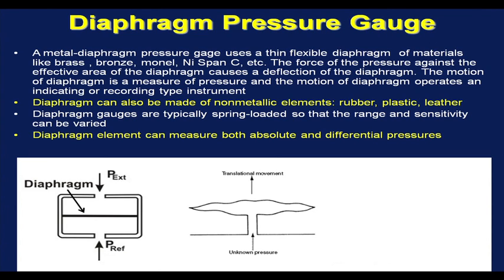Let us now talk about the diaphragm pressure gauge in a little more detail. A metallic diaphragm pressure gauge uses a thin flexible diaphragm of materials like brass, bronze, monel, nickel span C, etc. All these materials have very good elastic property. The force of the pressure against the effective area of the diaphragm causes a deflection of the diaphragm. The motion of the diaphragm is a measure of pressure, and the motion of the diaphragm operates an indicating or recording type instrument.